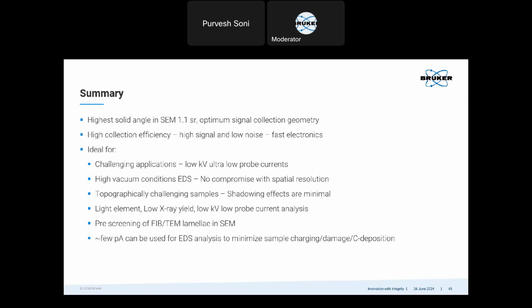This detector is ideal for challenging samples where you really need low kV and very low probe currents, and still get very high resolution, and maybe also minimize charging for, let's say, beam sensitive samples. Because of the low probe currents, you can still use high vacuum conditions, so you don't compromise on spatial resolution when you use the flat quad. And with the four segment design placed annularly, you have no problems if there are topographic samples or shadowing samples. I also showed that you could detect as low as boron with this detector.